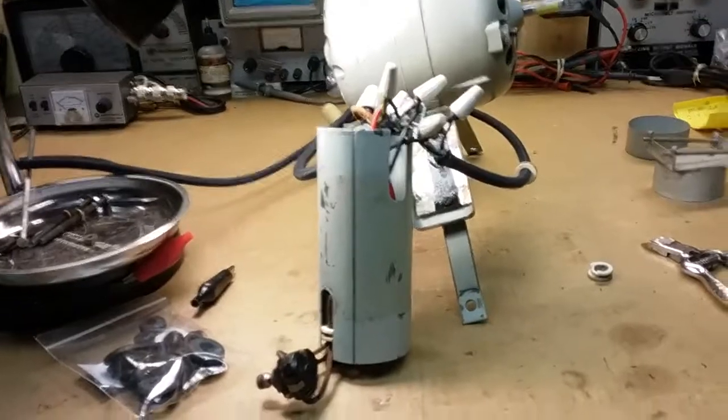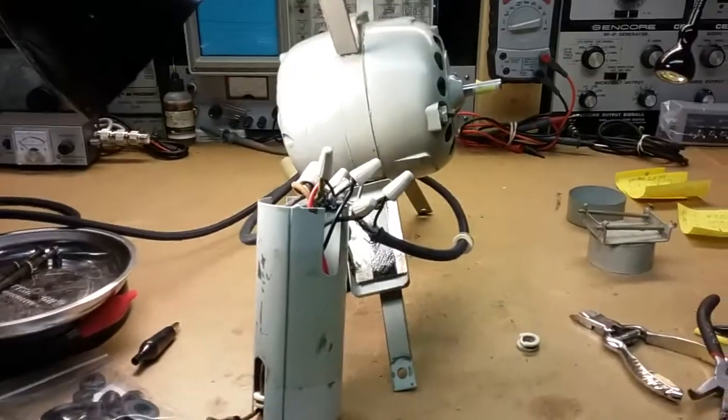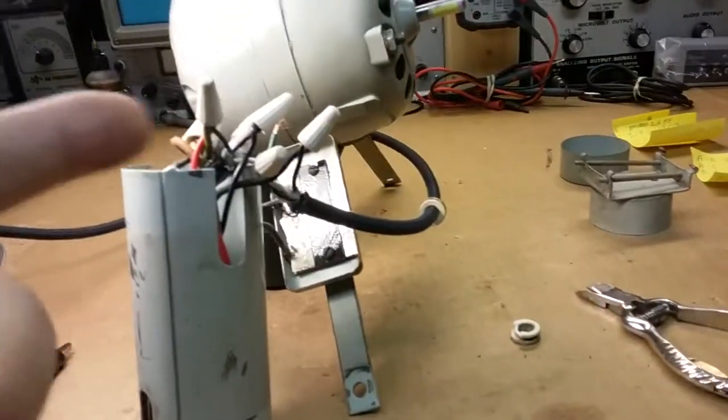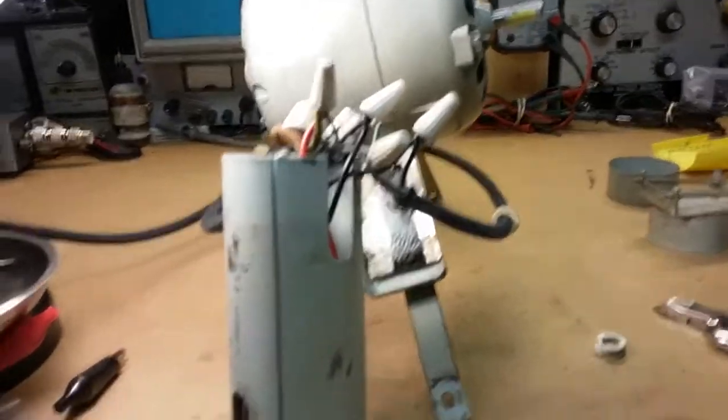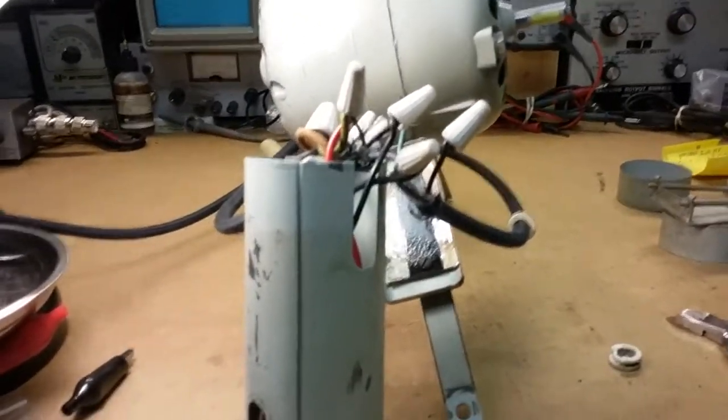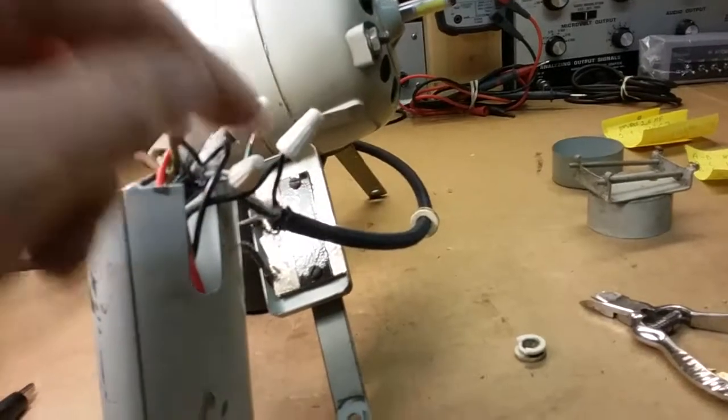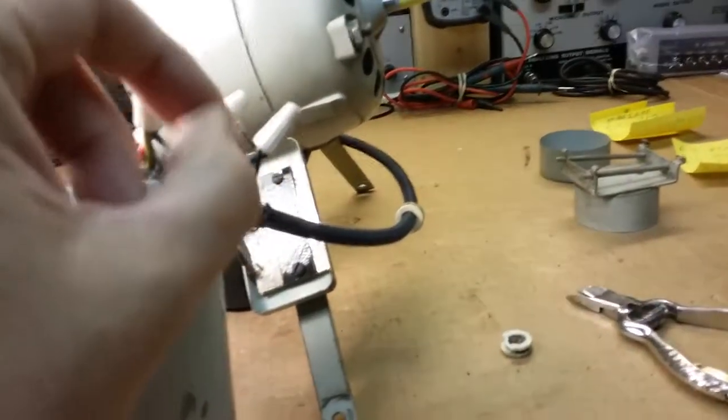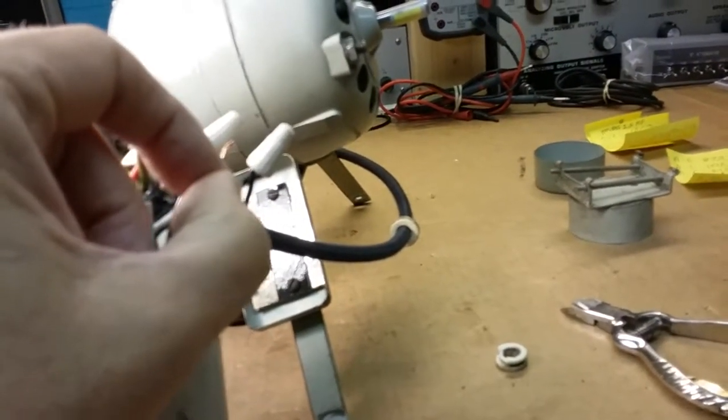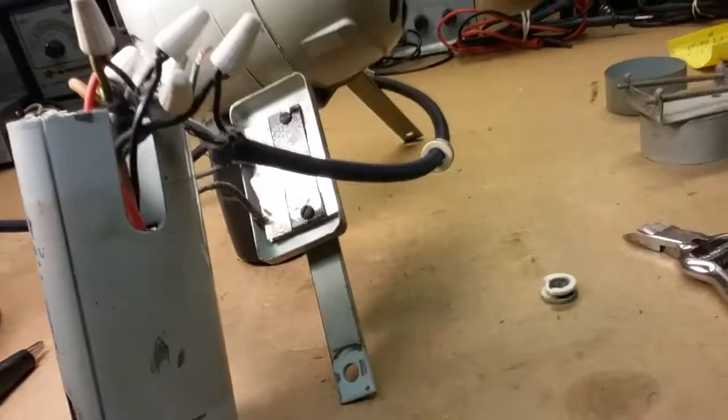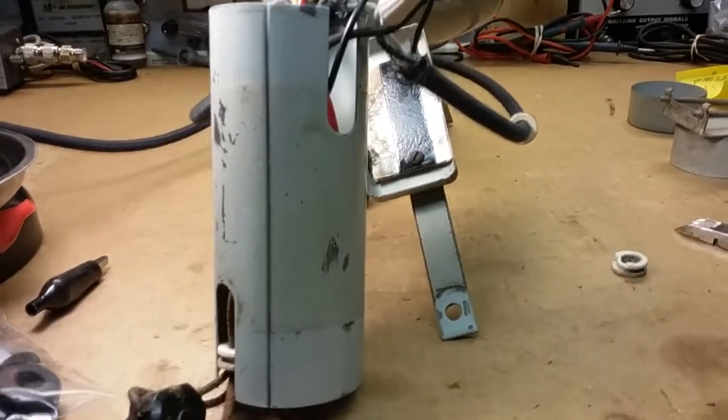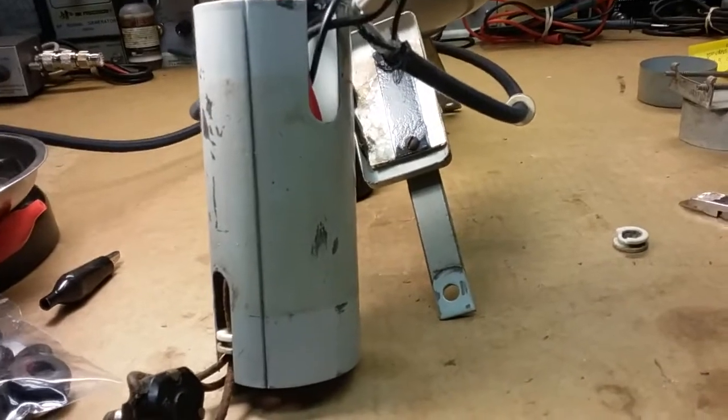Okay, I got this motor back together. Basically, all I got to do, they put ceramic caps on them, which are fine, but to ensure that they don't come off, I'm going to put electrical tape around them and a wire tie at the wire end. And that'll hold them on. Solder the ground wire to the case, which will give us the ground. And anyway, I got it in, I got a new head wire in, and a new line cord with a new plug.